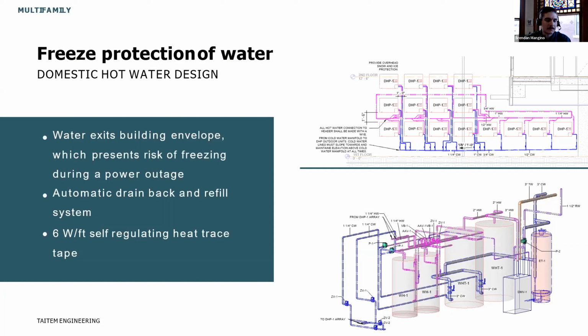Second, when the power goes out, the way we deal with freezing is we have an automatic drain back system. So this incorporates some normally closed and normally open zone valves that will revert to their natural state when the power is lost, and then some automatic air vents and vacuum breakers that allow for water to be purged from the system and air to be purged from the system when the water naturally refills at street pressure.